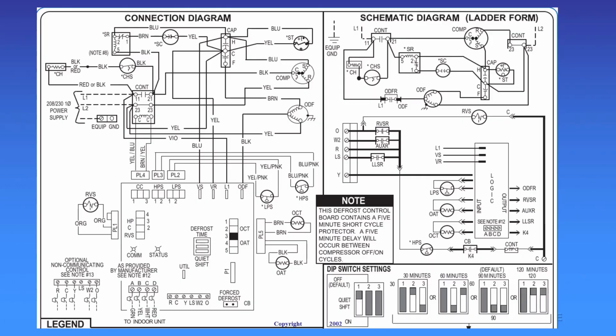This is a current diagram of a unit that has a control circuit board in it. You have your connection diagram on the left that shows where all the wires are landed that we have talked about before. And on the right is the ladder diagram, which shows how everything is connected electrically. You'll also notice that a lot of things are just inputs and outputs of the circuit board, which is where all of your logic and commands come from. Down at the bottom, you have some dip switch settings, and you also have your note that is available on the diagram.